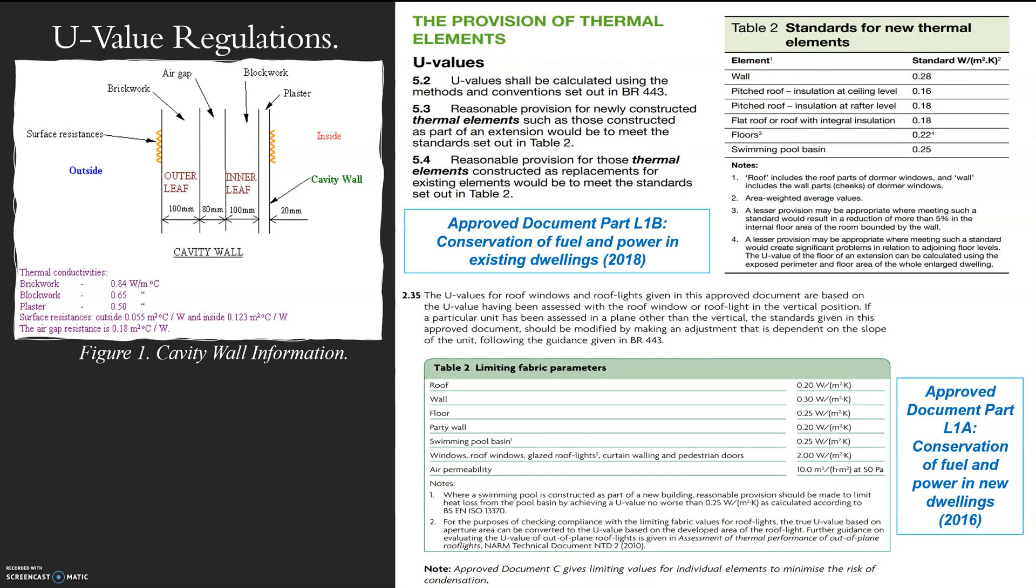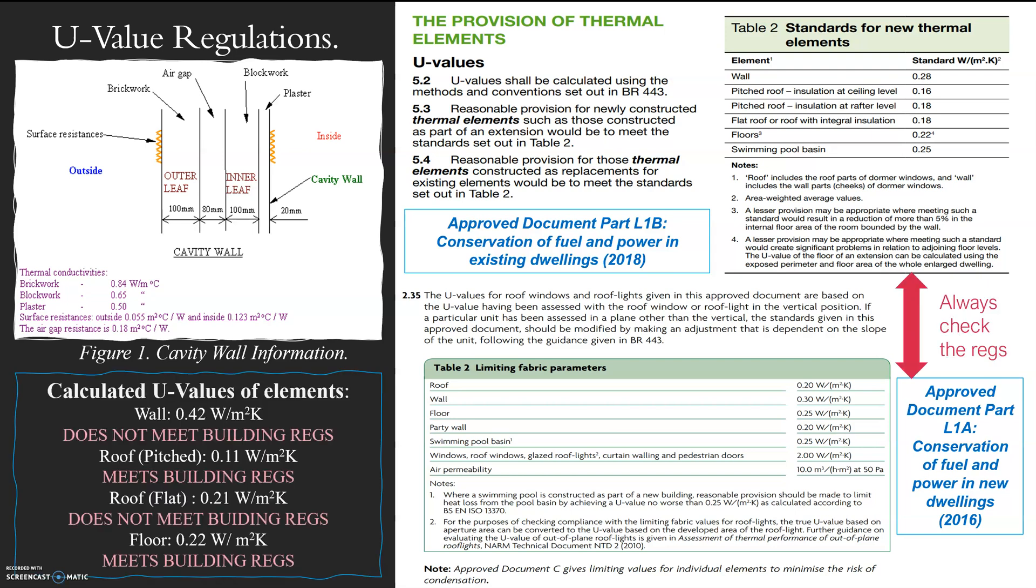And then very quickly, just looking at this concept, we have the regulations now. Very important always to check the regs because they do change. This part L1B proof document is 2018. L1A is 2016. L1B is for existing dwellings and L1A is for new dwellings. So if you have a look, the wall is different. 0.28 is your minimum for that and 0.3 is your minimum for that one. So just be very aware that I've got calculated U-values of elements here. Some of them meet the regs and some of them don't.